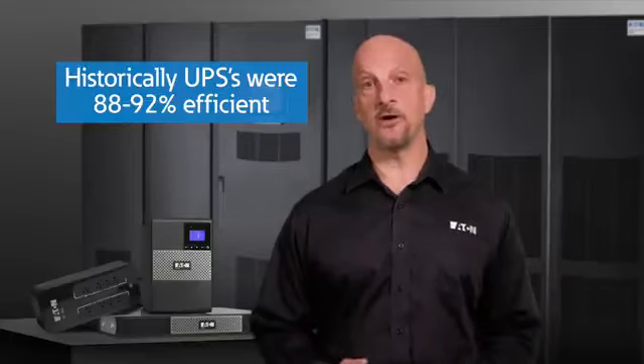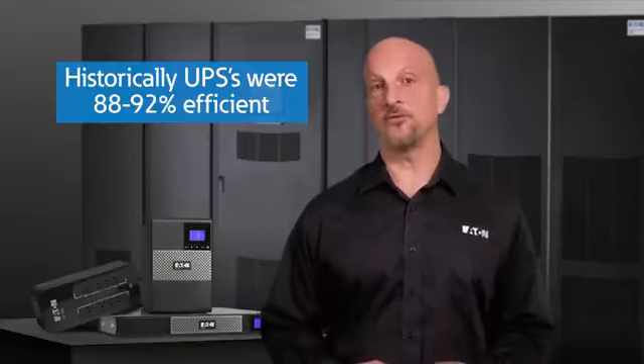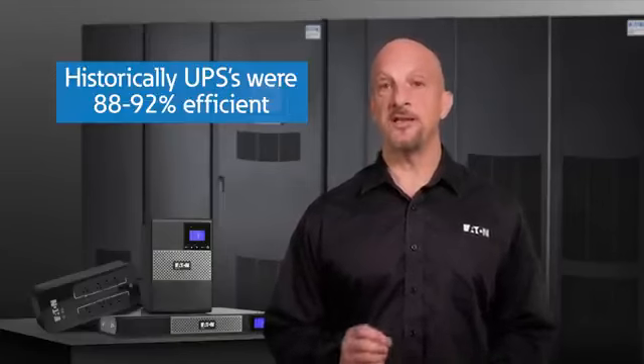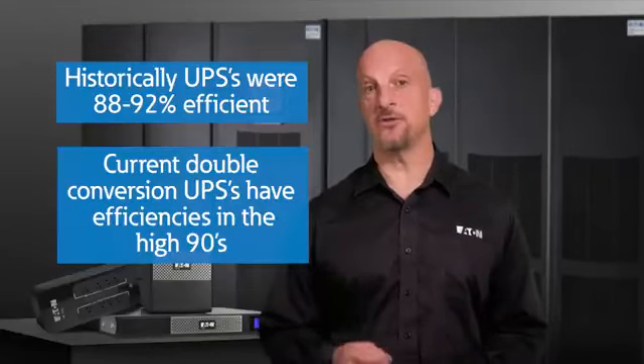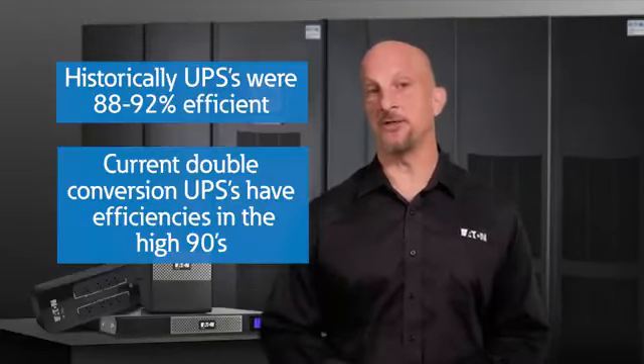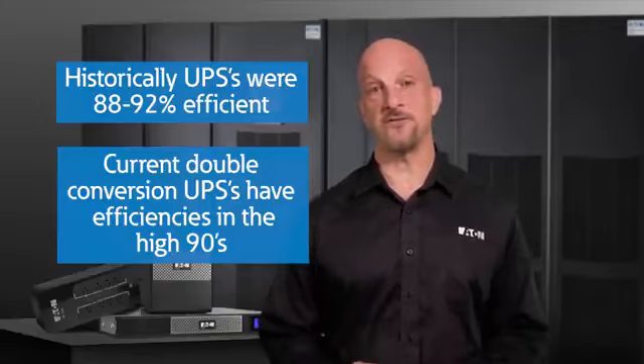Historically, UPSs were very lossy, 88 to 92% efficiency, for example. But today, you can buy a double conversion UPS with efficiencies well into the high 90s, allowing double conversion to be a cost-effective solution. Based on the 3 types of UPS topologies, standby, line interactive, and double conversion, which should you select for your application?